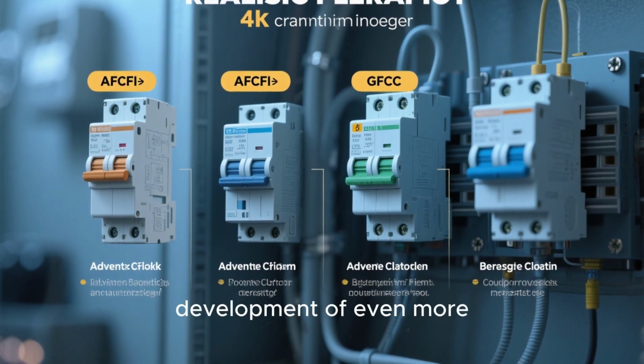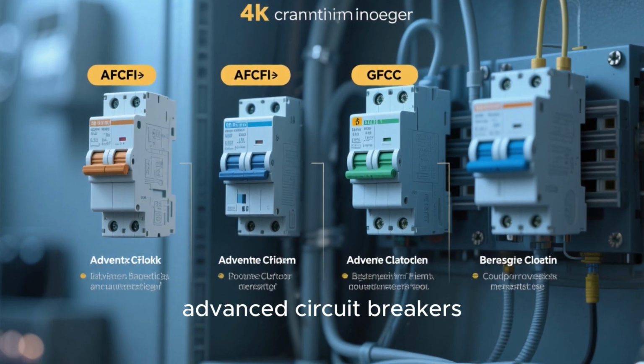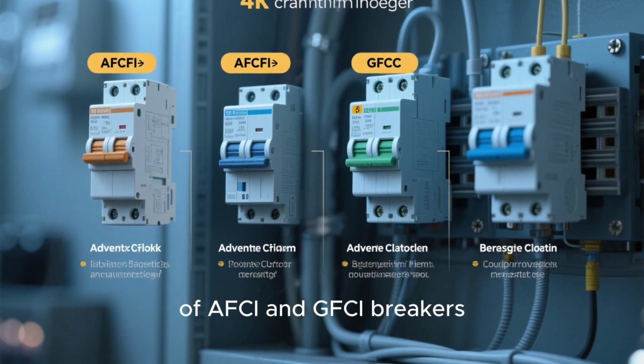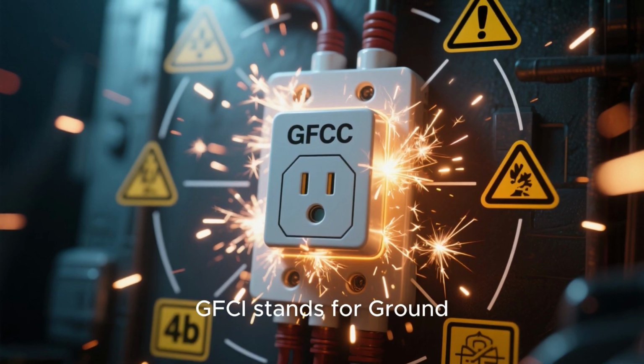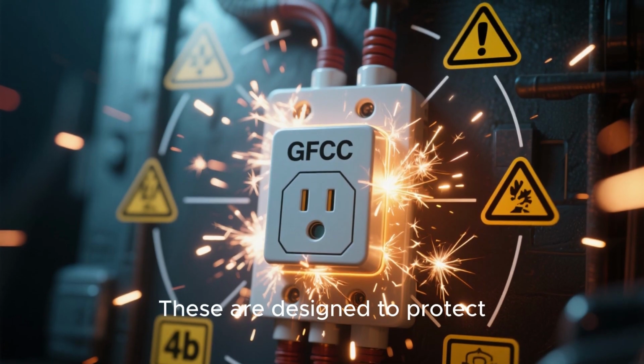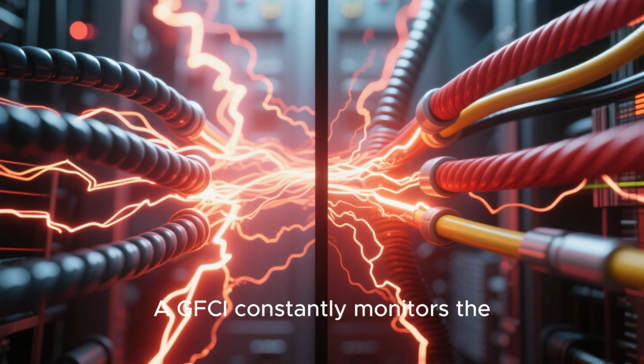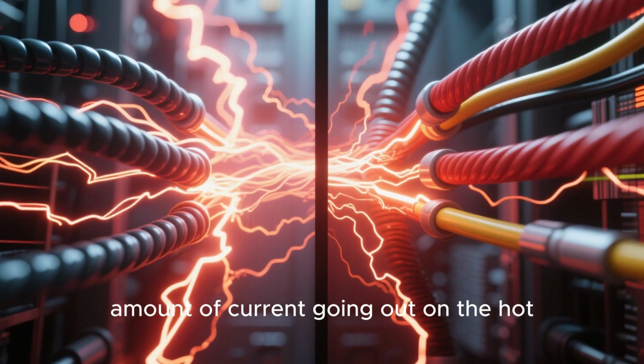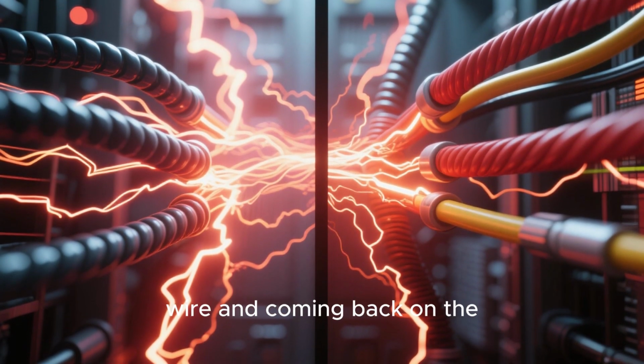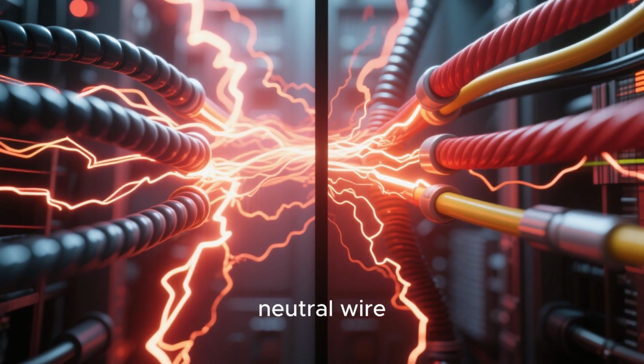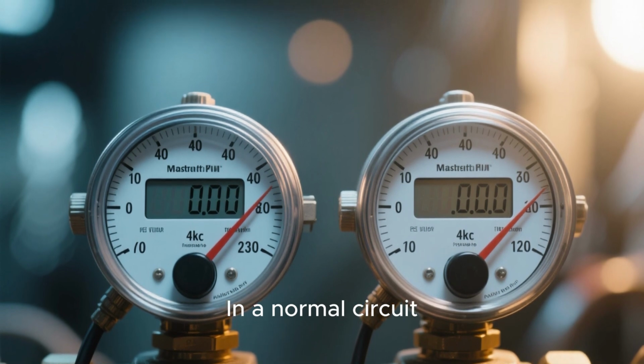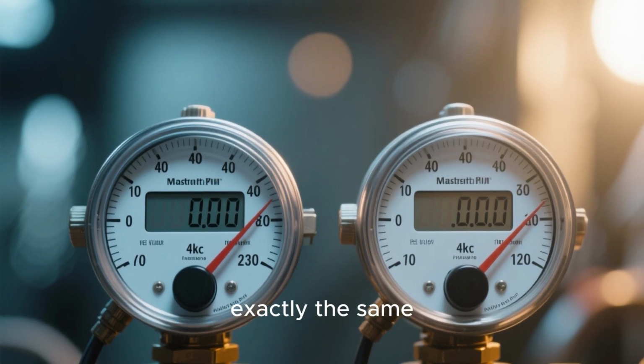In recent years, we've seen the development of even more advanced circuit breakers. You might have heard of AFCI and GFCI breakers. GFCI stands for Ground Fault Circuit Interrupter. These are designed to protect people from electric shock. A GFCI constantly monitors the amount of current going out on the hot wire and coming back on the neutral wire. In a normal circuit, these two amounts should be exactly the same.